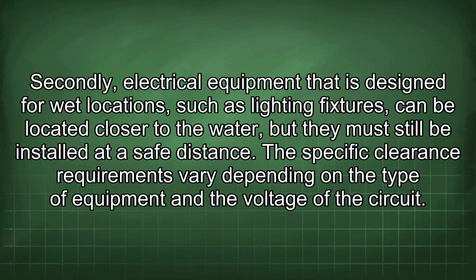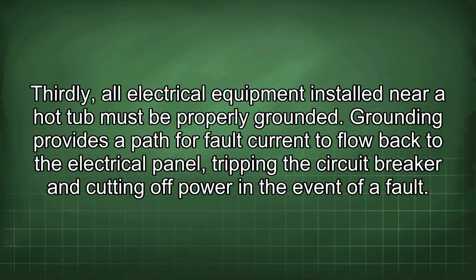Secondly, electrical equipment that is designed for wet locations, such as lighting fixtures, can be located closer to the water, but they must still be installed at a safe distance. The specific clearance requirements vary depending on the type of equipment and the voltage of the circuit. Thirdly, all electrical equipment installed near a hot tub must be properly grounded. Grounding provides a path for fault current to flow back to the electrical panel, tripping the circuit breaker and cutting off power in the event of a fault.